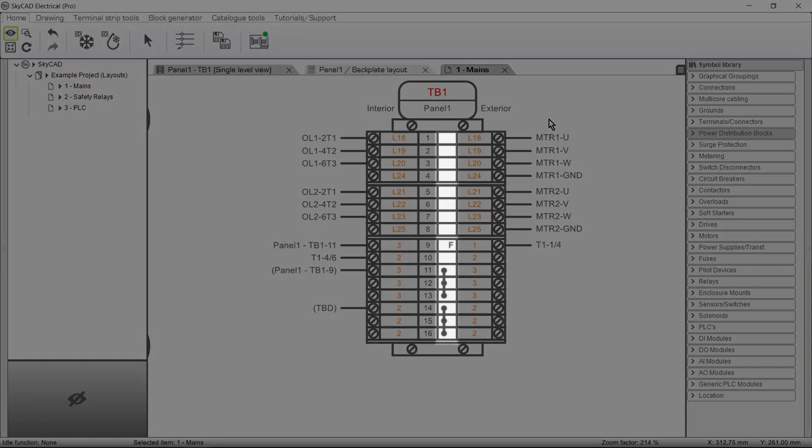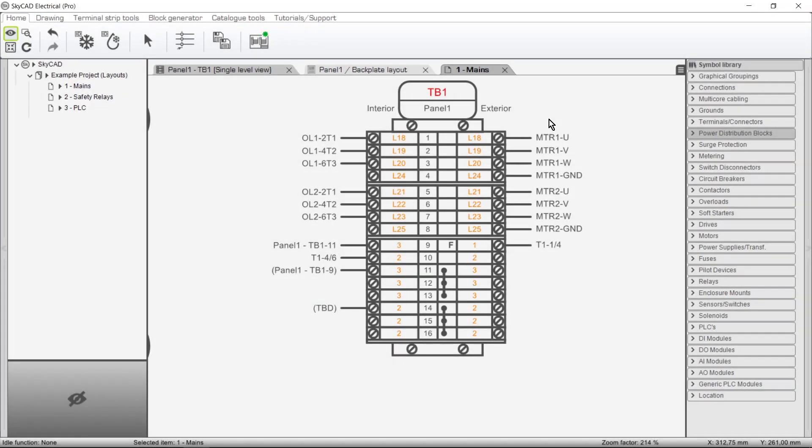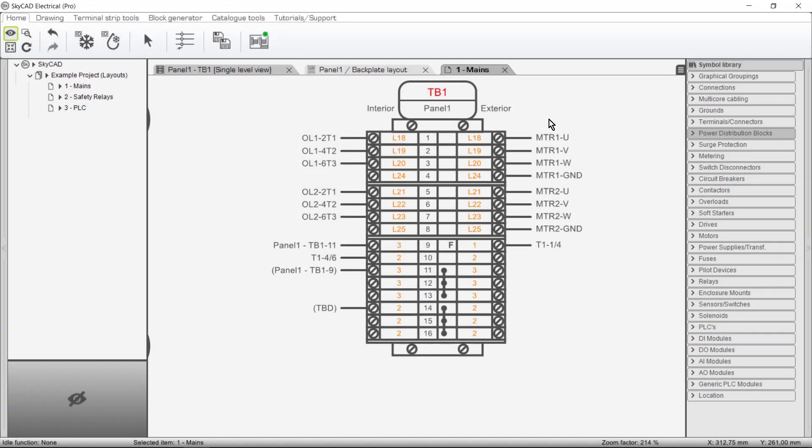This column indicates Fuse Terminals, or terminals that have been bridged. Please note that Fuse Terminals need to have a Fuse in it for an F to be displayed in this column. If you see some information in brackets, such as this, it represents that clarification is required if you wish to have a fully detailed Terminal Strip layout.